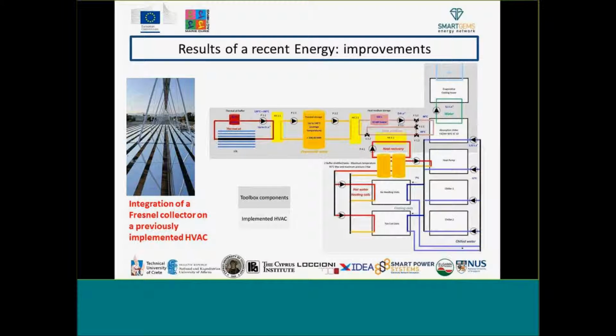To address the drawbacks identified by the energy audit, a Fresnel collector has been installed on the roof of a building close to our building, the Novel Technology Laboratory, in order to reduce the energy consumption for HVAC, mainly cooling in summer. This is a schematic of our already existing HVAC system, on a white background, and what we are now implementing, on a gray background. It relies mainly on thermal storage, which is able to store the heat produced by the Fresnel collector for at least 2 hours. This also ensures continuity of working and provides cooling to the building.